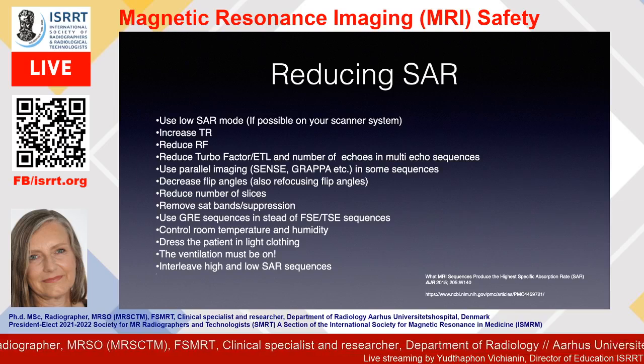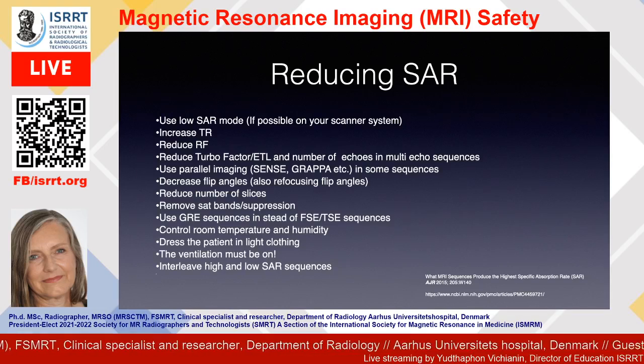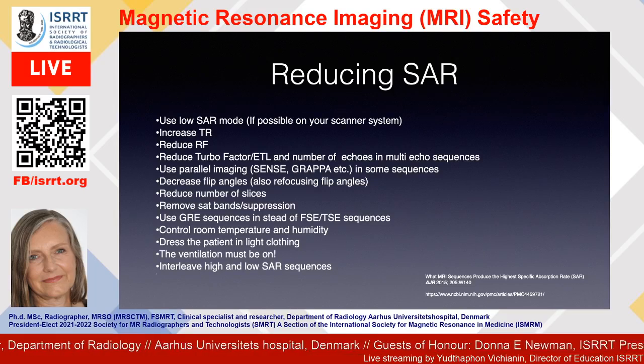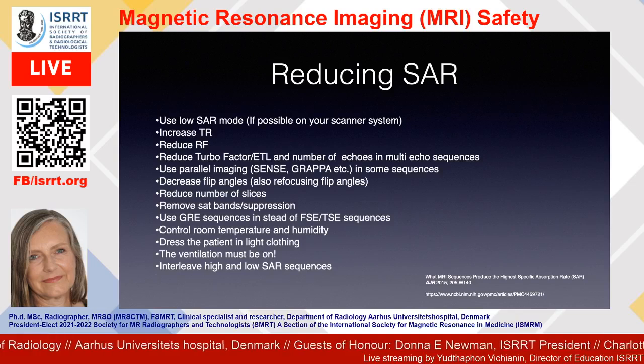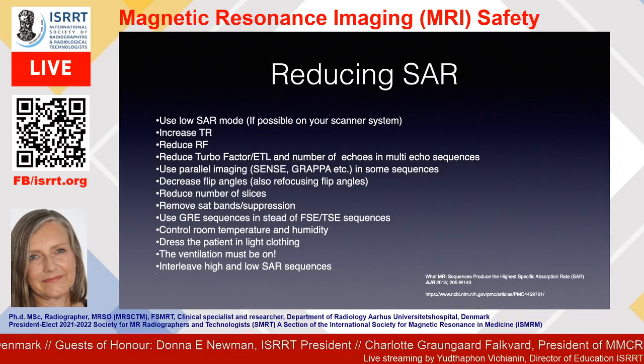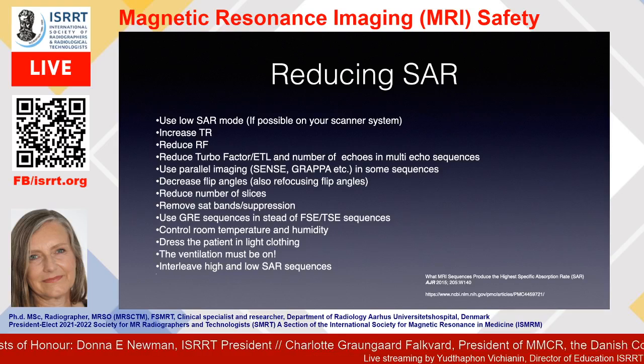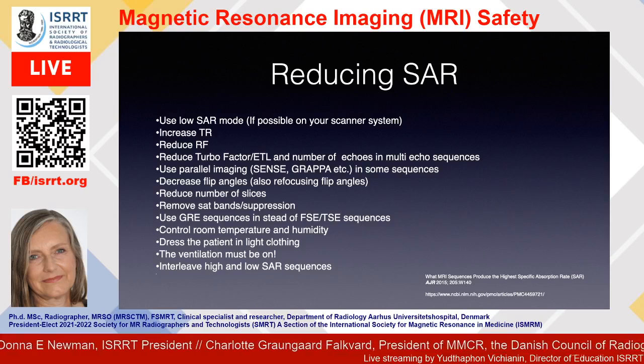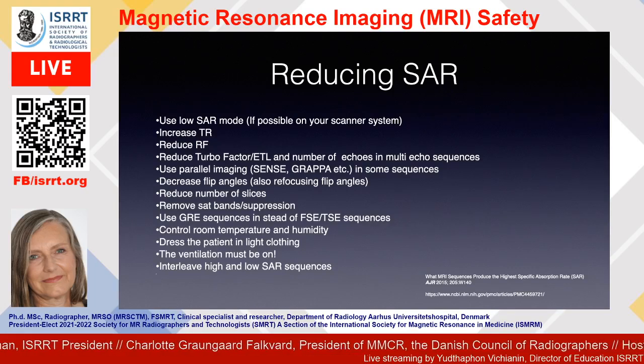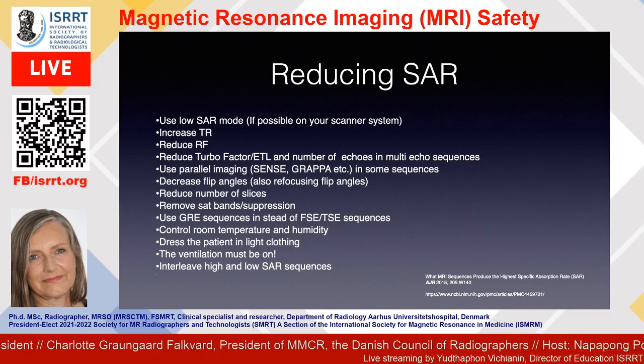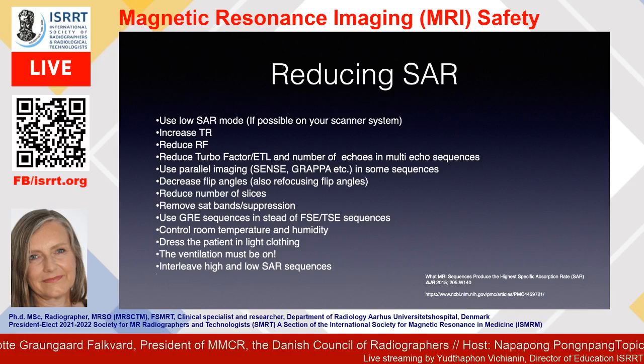You can of course increase the TR and reduce RF. That can be done, for instance, by reducing the turbo factor or echo train length and the number of echoes in multiple echo sequences. You can also use parallel imaging where appropriate, and you can decrease flip angles and of course also the refocusing flip angles, reduce the number of slices, remove sat bands or suppression bands, and use gradient echo sequences instead of fast spin echo or turbo spin echo sequences. And of course keep the room temperature low and also control the humidity. Dress the patient in light clothing and make sure that the ventilation fan is on, and you can of course interleave high and low SAR sequences.